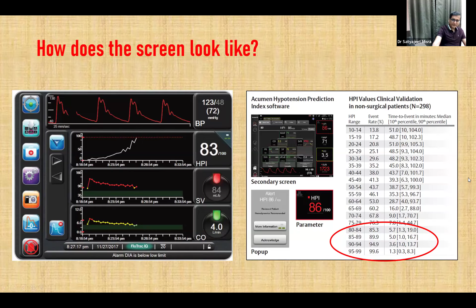If you look at the chart on the right panel, at the bottom numbers, anytime it starts hitting 85, the time to the index event comes down to roughly 5 minutes. So if it's 85, in the next 5 minutes there's going to be a hypotensive event. And as the number increases, the time to the index event comes down. When you have a number around 94 and above, the time to the event is less than 3 minutes. And when you have two such high values consecutively within 20 seconds, it is going to prompt you to review the secondary screen to discriminate what the cause of hypotension is.